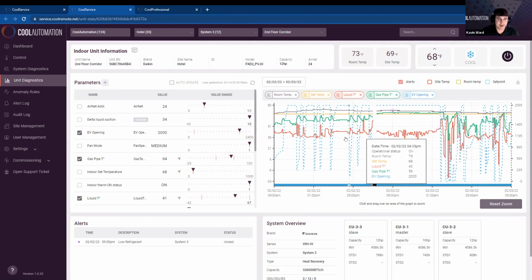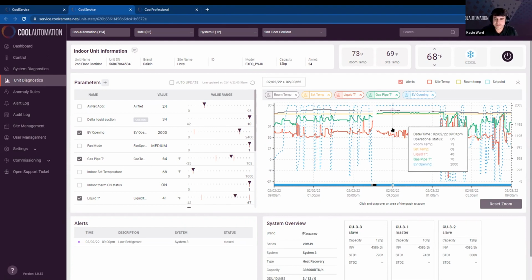At this point, I'd also like to talk about set point management. Overall, the majority of our service calls are going to be, it feels warm or it's too cold if the system's in heating. Essentially, the set point is not satisfied. The system is not operating as it should for your customers.